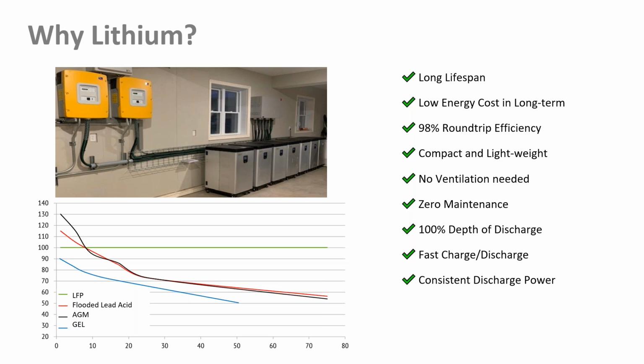Next slide, please. So when we look at why lithium, I think it boils down to maybe 8 or 10 key facts. The first thing is the long lifespan. I mentioned 6,000 cycles versus 3,000 cycles versus 1,500 cycles, and then the low energy cost in the long term. So although with lithium iron phosphate you may pay a little bit more upfront, because of the longevity and the high cycle life you're actually paying less per kilowatt hour versus another option or even a lead acid option. It has a very high round trip efficiency at 98%, and it's very compact and more lightweight than a lead acid battery or another lithium battery.